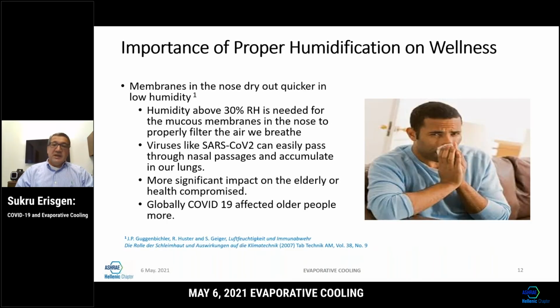So what happens when the humidity is low or very high? Membranes, our nose, dry out when relative humidity gets lower. Why am I talking about that? I'll get into that in a little bit. Humidity above 30% RH is needed for mucous membranes in the nose to properly filter the air we breathe, because that is an important defense mechanism our body has.